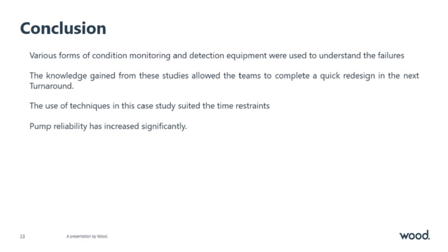Before, I mentioned that the MTBF was 1300, and that was a measure from say 2012 until 2018, where about 19 pump heads had been changed in one location for one tag, and the MTBF was as low as 1300. That's the average. But of course, after the study, things changed, and I'm pleased to report that the first pump change after the pipework redesign reached 10,000 hours, no problem.